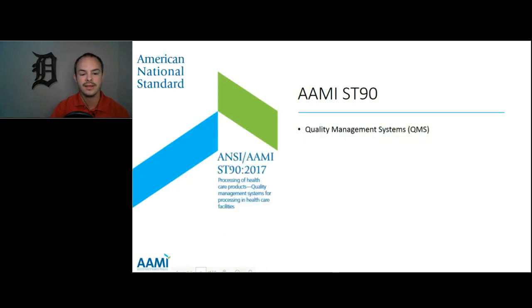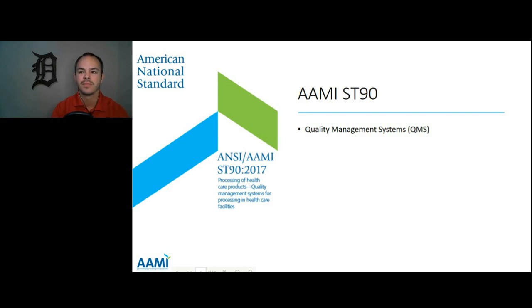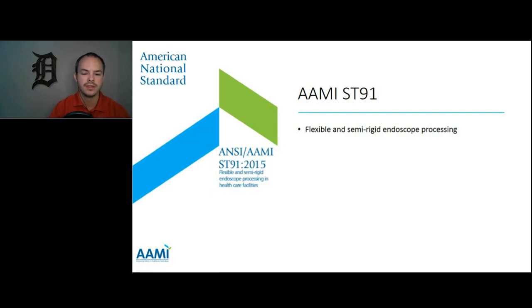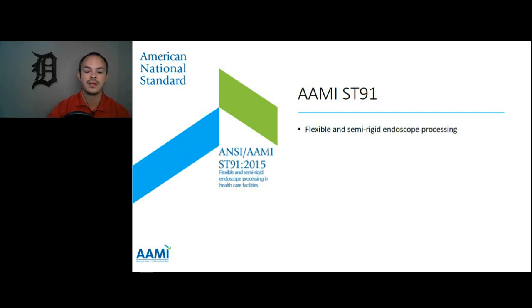ANSI/AAMI ST90 is a quality management system for processing in healthcare facilities. A quality management system is extremely important because our processes are filled with opportunity for failure. ANSI/AAMI ST91 provides guidelines for flexible and semi-rigid endoscope processing. For the purposes of this standard, healthcare facilities means endoscopy centers, hospitals, nursing homes, extended care facilities, freestanding surgical centers, and ambulatory health centers like clinics. All of these areas are encompassed in this standard.